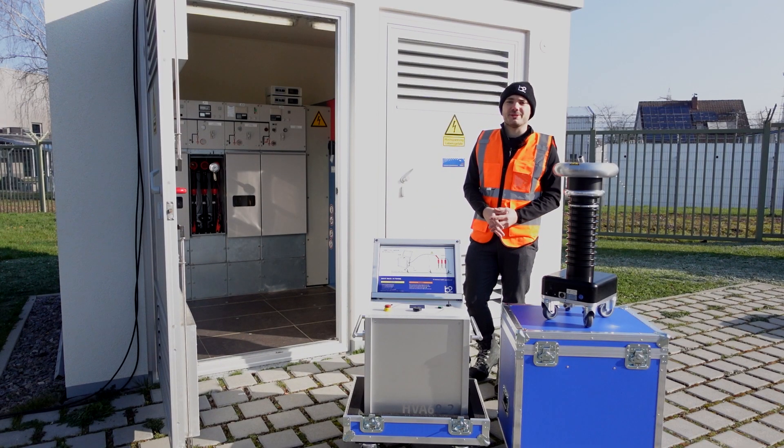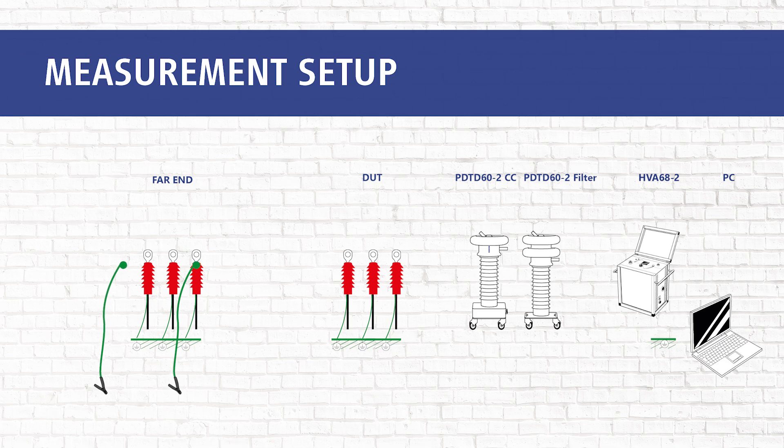Now we start with our measurement. Please ground the far end of the not tested phases and apply the same rules for the phases to be tested on the far end as the near end, like corona shields and the distance to other potential. The far end connections are not included in this video and will be included in a later video.